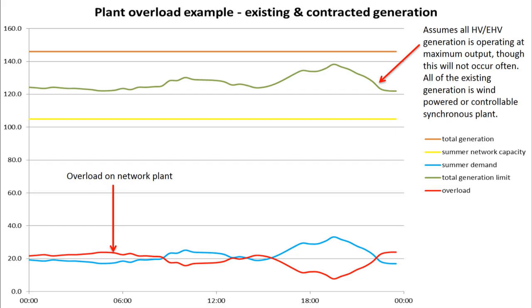And combining this, i.e. adding the values to the summer network capacity, so the yellow and blue lines together, this gives us the green line up here, which is the total generation limit throughout the day. As you can see on this day, the total generation capacity line in brown up here exceeds the total generation limit line down here, and subtracting the generation limit from the generation capacity line gives us a profile for the potential overload, which is down in red at the bottom here. Again, you can see how that fluctuates throughout the day, and that's dependent on what demand, the actual consumption of electricity in the network, is doing throughout the day.